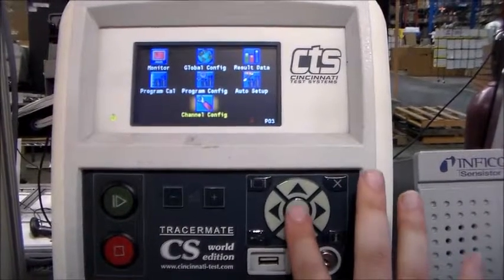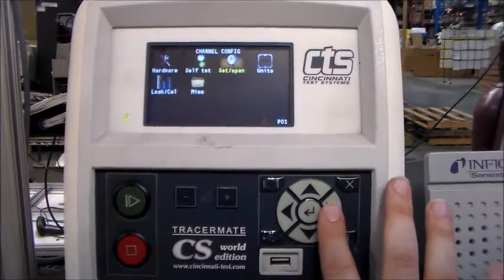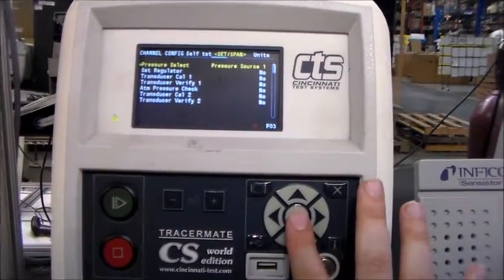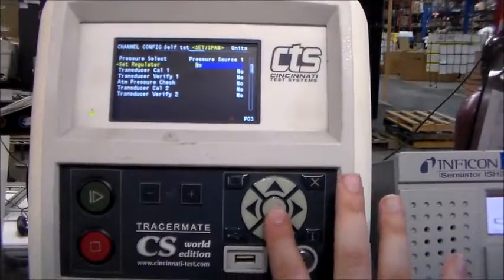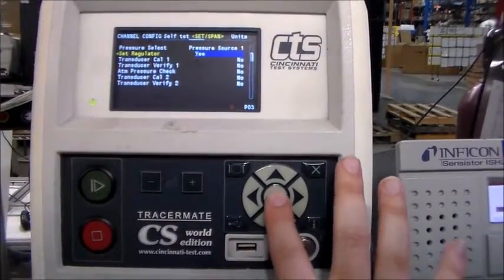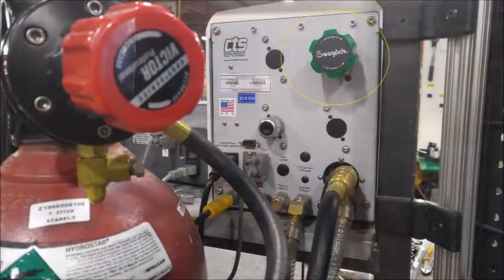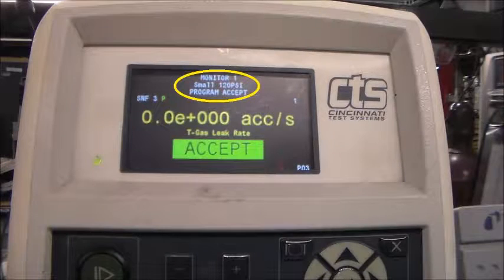Then, using the arrows and OK button on the panel, select Channel Config, then Set/Span. Then scroll down to Set Pressure Regulator and hit OK. Change the input to Yes, then press Enter again. Turn the large knob on the back of the TracerMate to the pressure required for the program you are using.